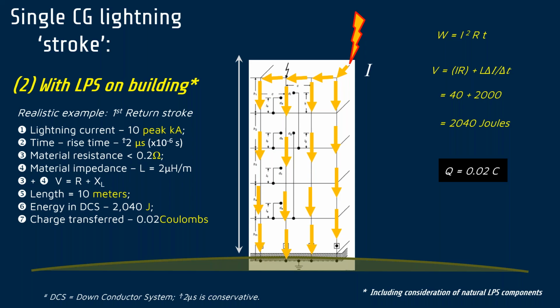Now, on power systems, that's okay, because there are zones of protection. On a shielded line, you've got a shield wire, and towers bond those shield wires to ground. You've got your earth resistance that you still need to manage. You don't get away from that. But you've got that first pass. So when you manage that soundly, you're cutting out 90% of the lightning activity. Anything else that is now too high causes a backflashover, or however the surge arrives at the substation.